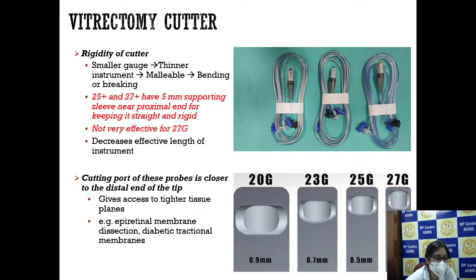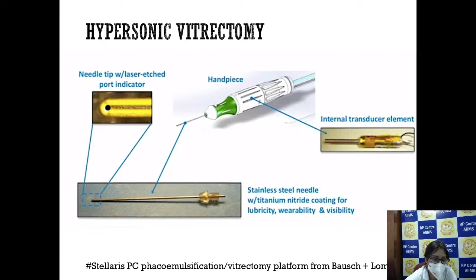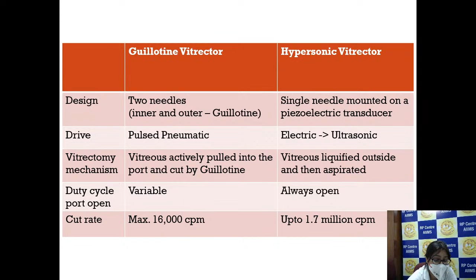Now the cutting port of these probes is closer to the distal end of the tip. You can see in 27 gauge the port is very close to the distal end, so it gives access to the tighter tissue plane. So the vitrectomy cutter can be used to remove epiretinal membrane, and in cases of diabetic tractional membranes. Now the recent innovation is a hypersonic vitrectomy cutter, which uses ultrasonic energy, and it has a 27 to 31 kilohertz frequency. It liquefies the vitreous and then it is aspirated inside, and so the duty cycle of the port is always open, and the cut rate is up to 1.7 million cuts per minute. Now we come to the aspiration.